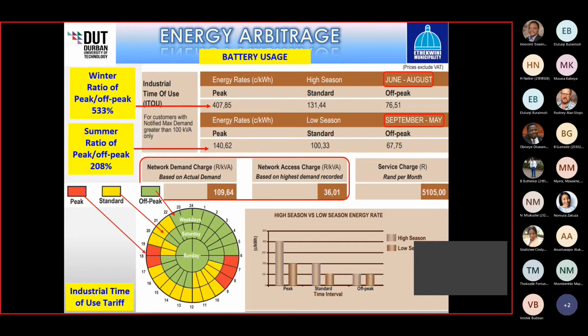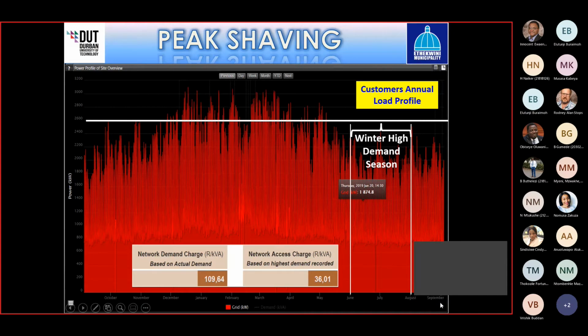If you can charge the batteries off-peak and discharge during peak, that is the benefit. Whilst in the summer months or low season, which is September to May, the rates are not as lucrative. If you look at the ratio of peak to off-peak, it's only about 2 to 1, or 208%, which is much lower compared to the 533%. But if we look at the customer's load profile on this slide, this is the annual one-year load profile. We can see that between June and August, the customer's load demand is much lower. This is typically because the cooling required by the customer is much lower in winter because of the lower temperatures, versus summer where you've got very hot weather and your cooling systems require a lot more energy to cool the buildings.